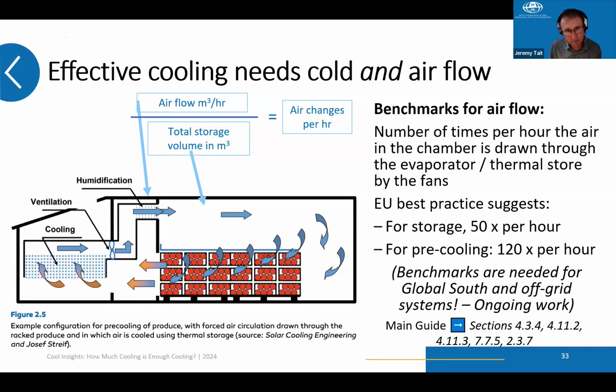Good practice for Europe generally suggests around 50 air changes per hour for storage. If you want pre-cooling, you'll need at least double that. 120 seems to tally with good practice advice for Europe and Indian government advice. It was surprising that these numbers weren't being discussed by many other equipment suppliers in this market.